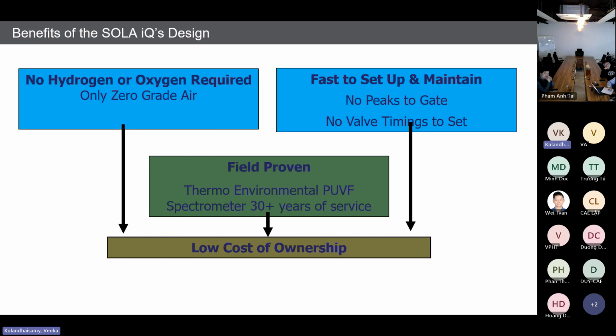So functionality, I already explained this. No need for hydrogen or pure oxygen. We use zero grade air for combustion, so we can reduce the running cost. Also, no peaks to gate. If you use a GC, you have to gate the peak, right? But here, no need to worry about peaks. No valve timing to set. If you have a GC to measure sulfur, you need to gate the peak and also select the valve timings accurately, otherwise you are not able to detect the sulfur. But in our SOLA IQ or SOLA 2, you don't need to worry about that. Field proven: the Thermo Environmental PUVF spectrometer has 30 plus years of service. It is proven already. Low cost of ownership and maintenance.